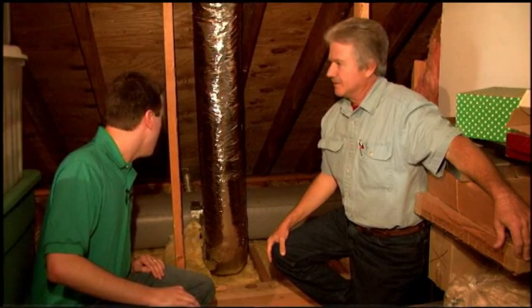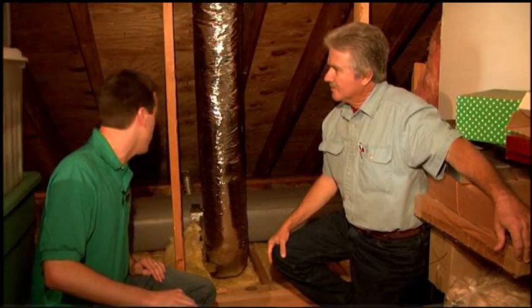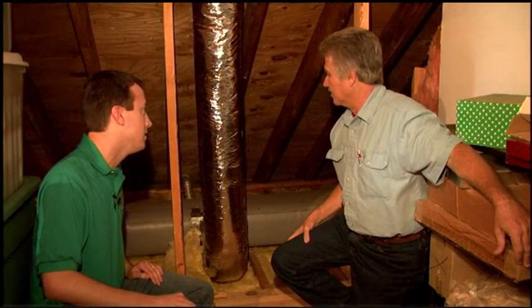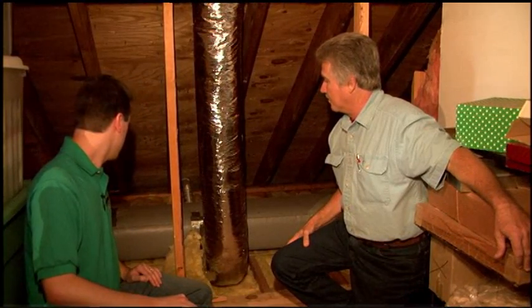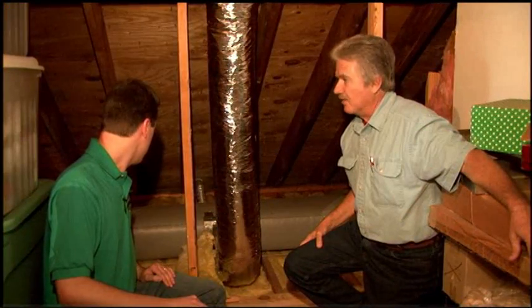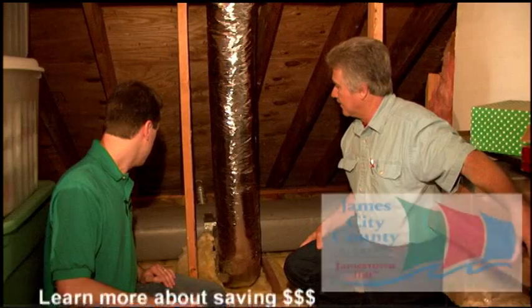So we're up in the attic now. Jay's run the blower door test, and he uses his infrared camera, and we've pinpointed some of the leakier areas of the house. Jay, can you tell us sort of what we're looking for up here? Sure. Several things. One, we're going to look for penetrations through the top plate, which would be plumbing runs, also wires coming through. We'll get air infiltration from the unconditioned area into your house through those spots, and we'll use a spray foam in that area as part of the air seal.